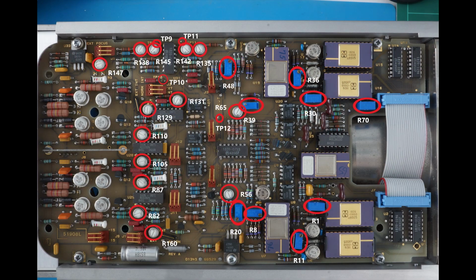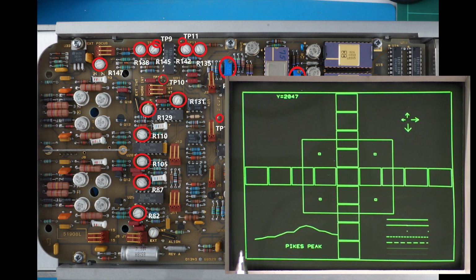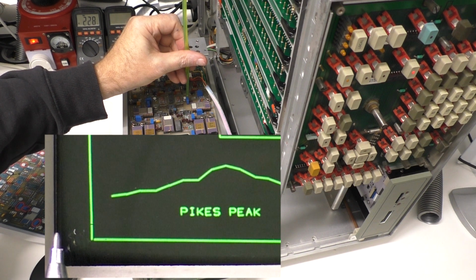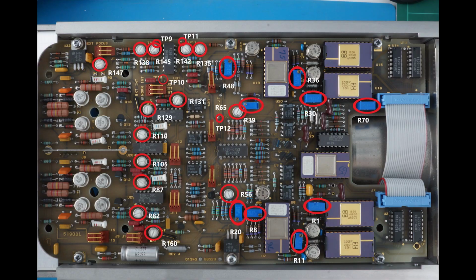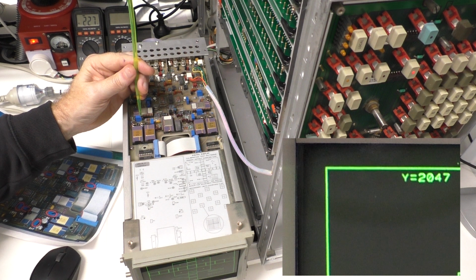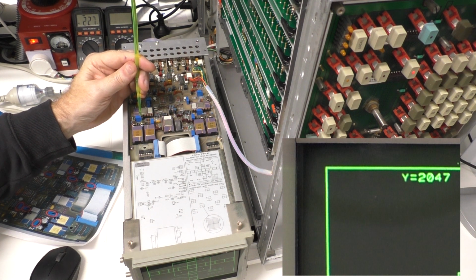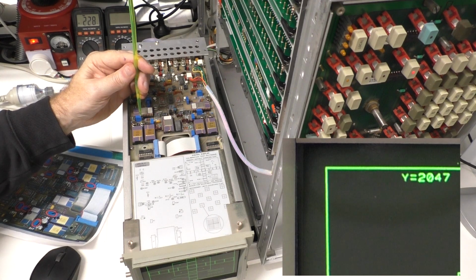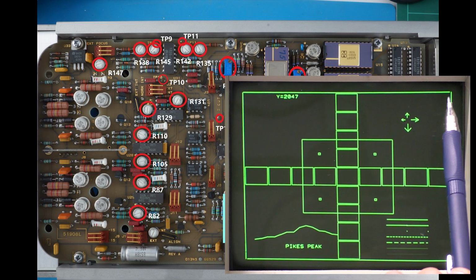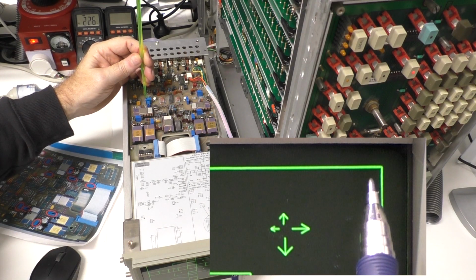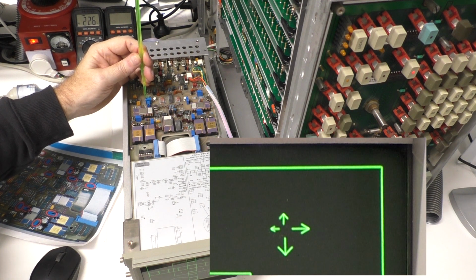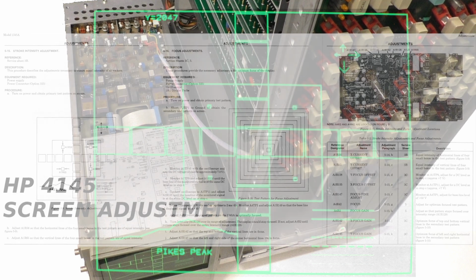Repeat this procedure for R39, so that the left vertical line meets the end of the bottom horizontal line. Repeat for R11, so that the top horizontal line meets the left vertical line. Finally, perform this procedure for R20, so that the top horizontal line meets the right vertical line. That completes the stroke generator adjustments. We will move on to section 5-15, stroke generator intensity adjustments.